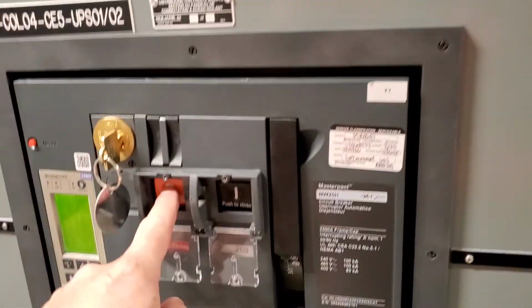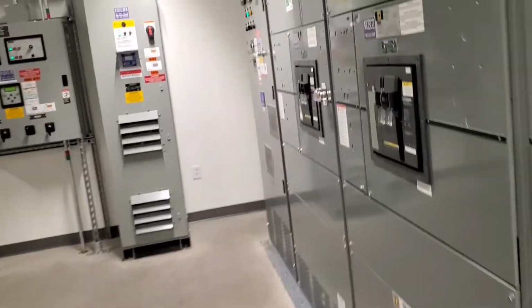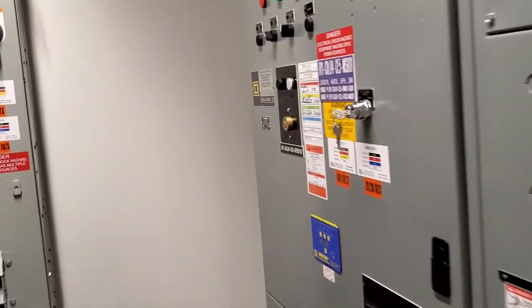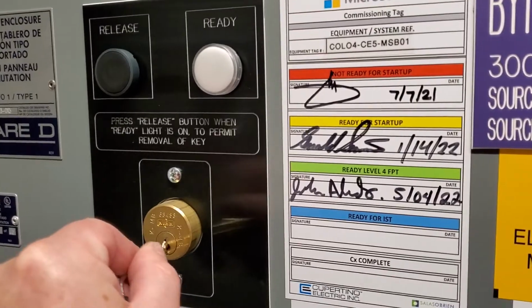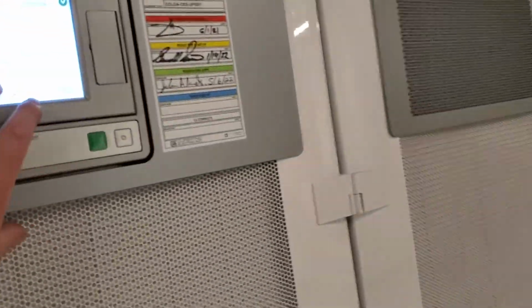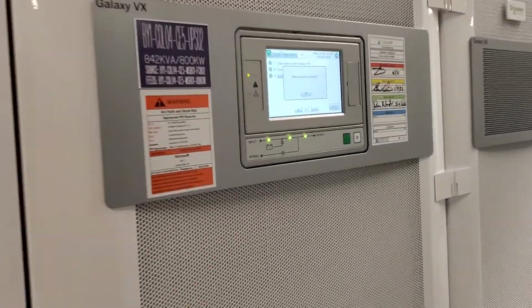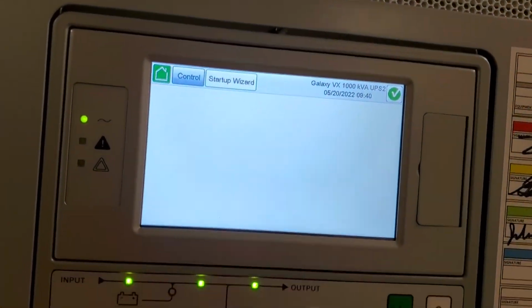Now I can open up the MBB, take the key out, and put it back into key release. This is part of the SKRU circuit. Once I put the key in and it's captured, the UPSs are online and we get all three green lights, and I've successfully started up both UPSs. Startup sequence successful.